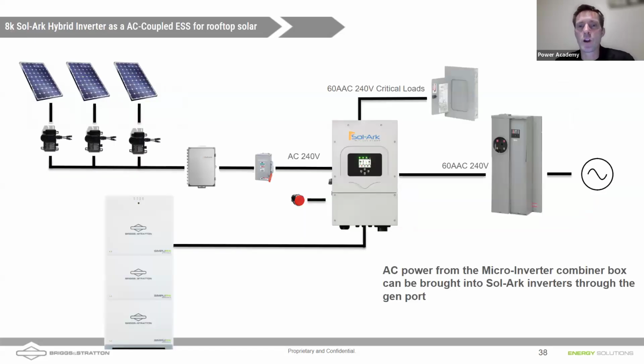So if we add a Sol-Ark inverter to a system on the roof like this, you might see this in retrofits. Customers signed up for solar power 10 years ago. They've got an existing Enphase microinverter array on the roof, but they're now looking to have battery backup, or power when the grid is down. We can do that with a Sol-Ark inverter, which is grid forming and has that transfer switch built in. The inverter will disconnect in a grid outage, but the batteries will allow it to do grid forming and create a signal that those microinverters can follow.